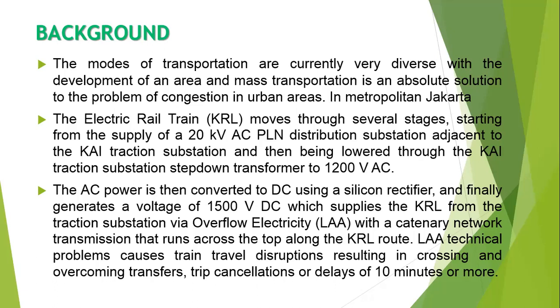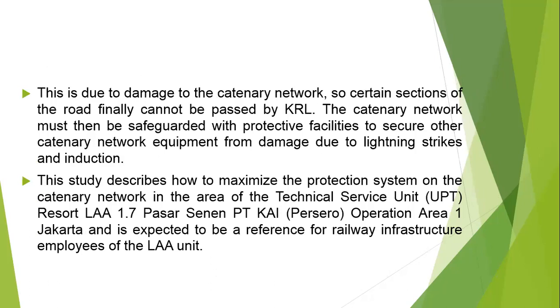LAA technical problems cause train travel disruption, resulting in trip cancellations or delays of 10 minutes or more. This is due to damage to the catenary network, so certain sections of the route finally cannot be passed by KRL. The catenary network must then be safeguarded with protective facilities to secure other catenary network equipment from damage due to lightning strikes and induction.